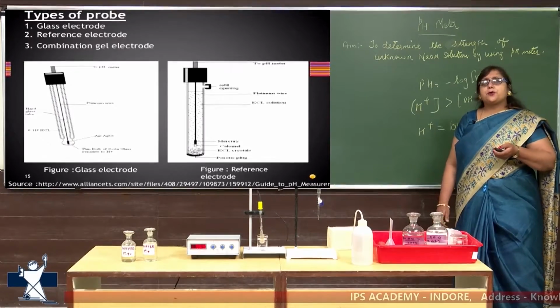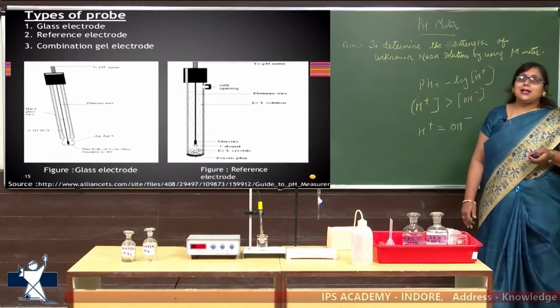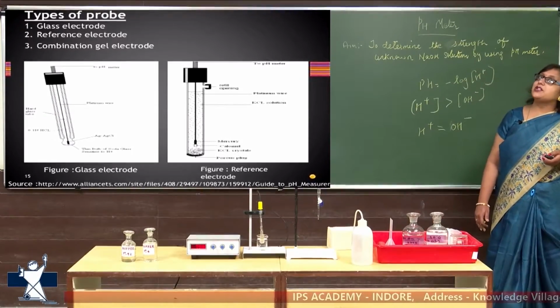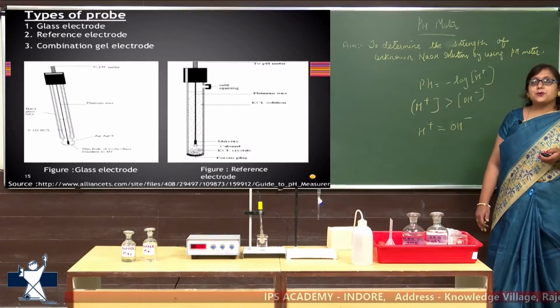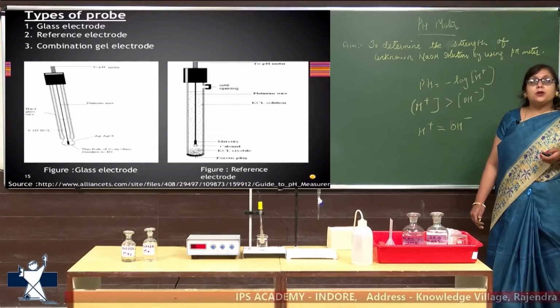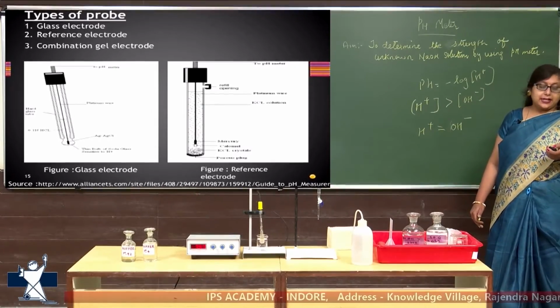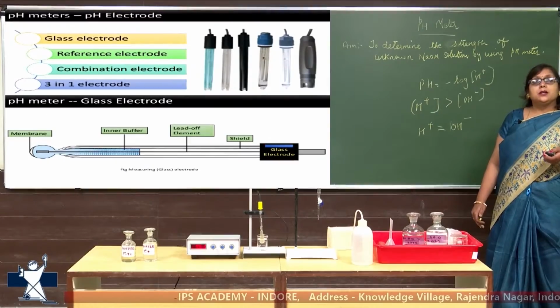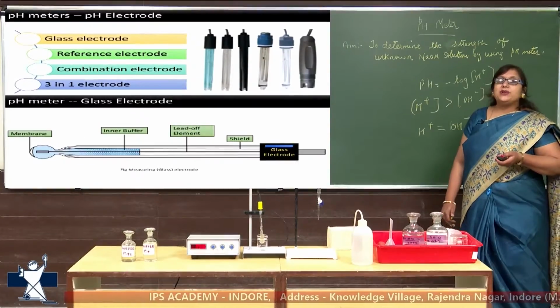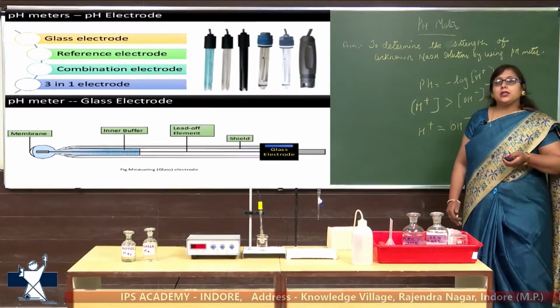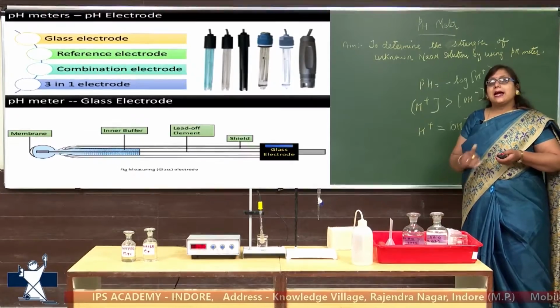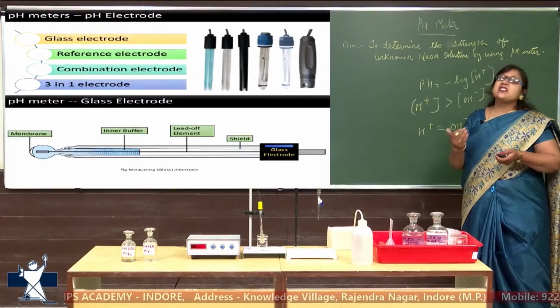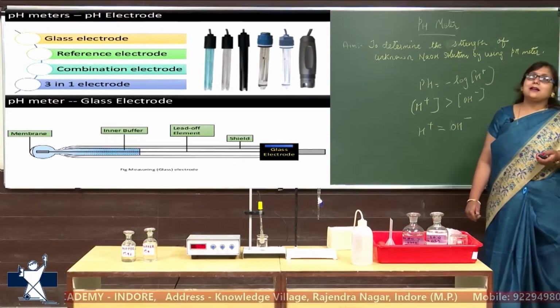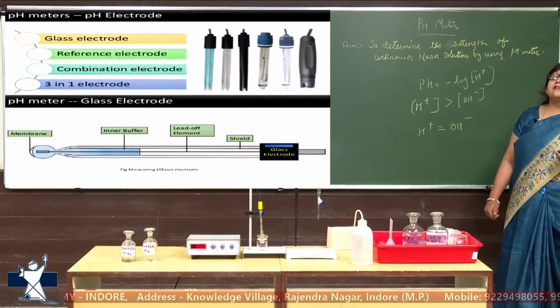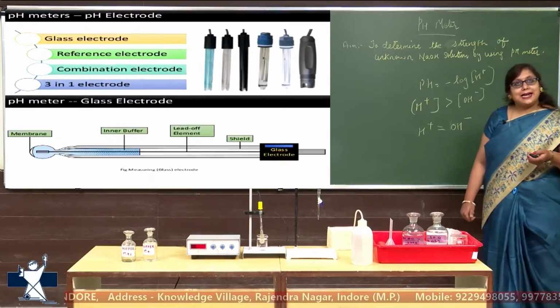Now, the types of probes which we use are the glass probe, the reference probe and the combination gel probe. The first one is the glass probe, the second is the reference probe. We will see detailed diagrams of these probes. This is the glass probe, which consists of a glass membrane. There is an inner buffer of KCl, and elements are present inside it. This is a glass electrode, and it is only responsible for the hydrogen ion activity.